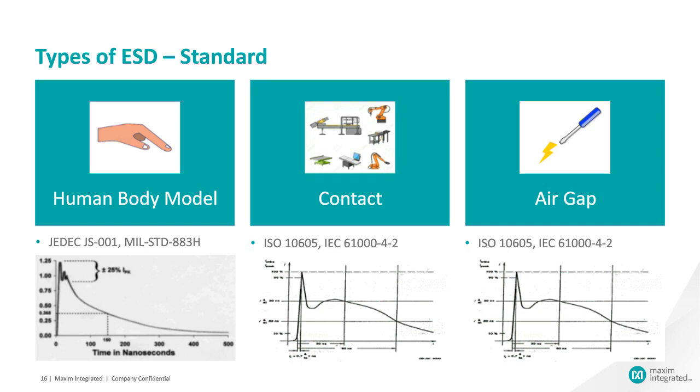peak in their waveform. For the human body model, we're talking about nanoseconds here, but in contact and air gap, we're talking more microseconds. For contact, the first peak is what we're looking at, and for air gap, it's that secondary peak we're looking at.